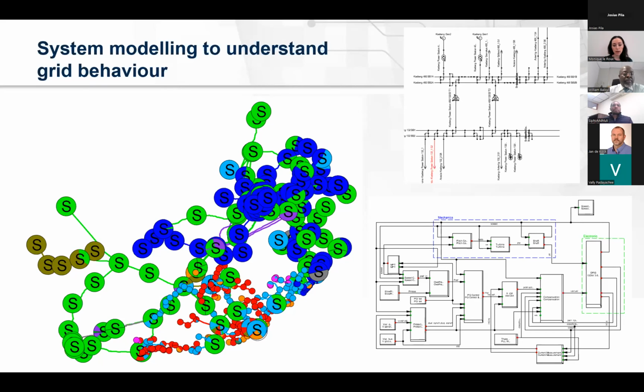And just maybe to the right, the control systems there, that's just an example of a generator that's on the Eskom network. The whole control system of the generator, every mechanism, every control system is represented there in full mathematical models. So whichever change you're going to bring about, every setting that's changed on the generator, every setting that's changed on the network can be modeled completely and accurately, which obviously is a very powerful tool for planners and operators to use, because that sort of gives you eyes into how you can operate your system and what's going to happen, without the need of that being implemented in practice. Next slide.